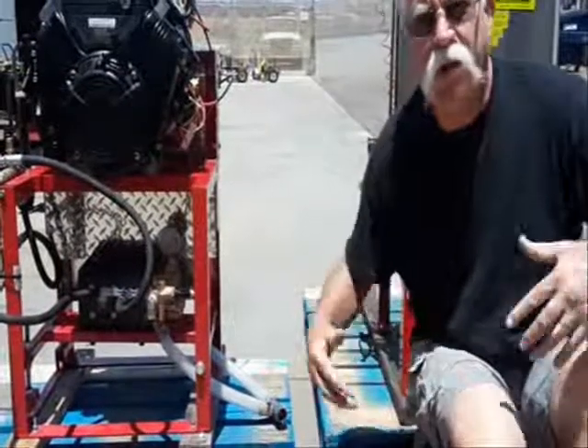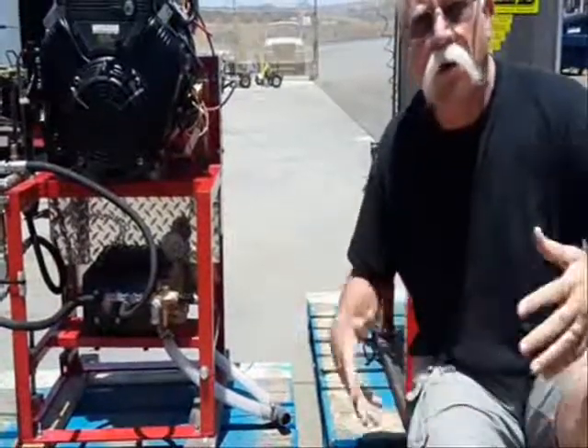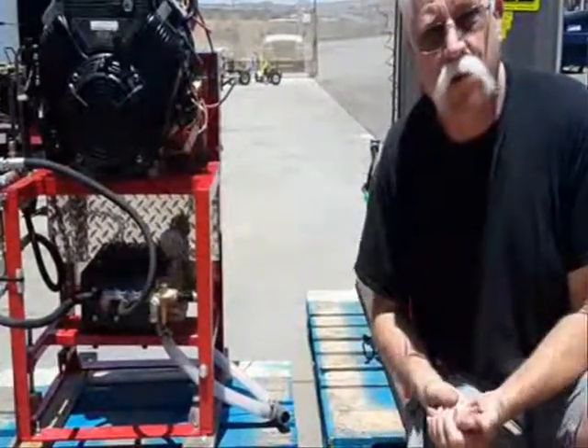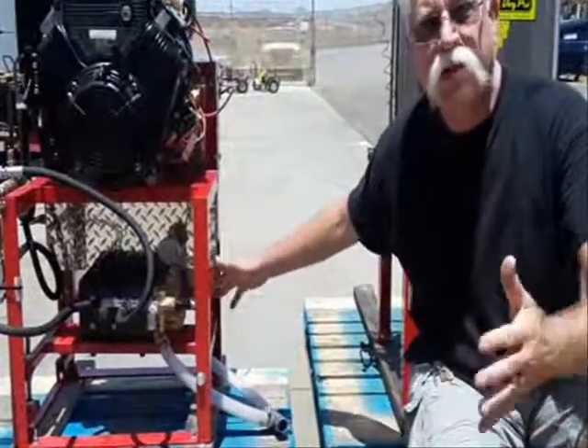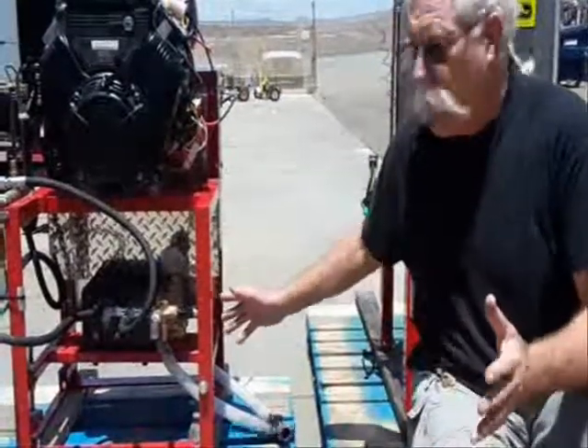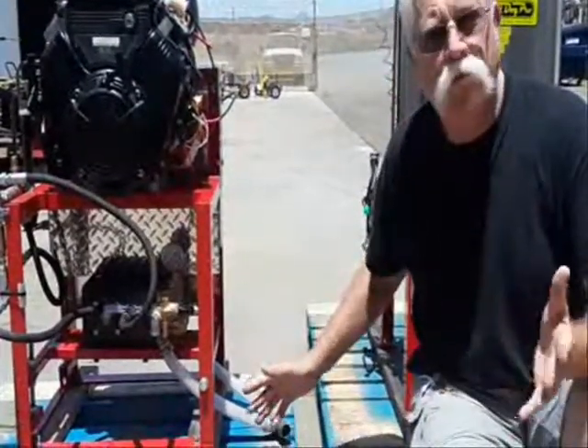If you were to call me up and say, my pump's not making pressure today and I'm getting pulsating pressure, what do I do? The first thing I'm going to ask you to do is pressure feed this thing to check for leaks. That's the first step in troubleshooting a pump. You've got to prove that it's got the perfect water supply, and then we can go on from there.